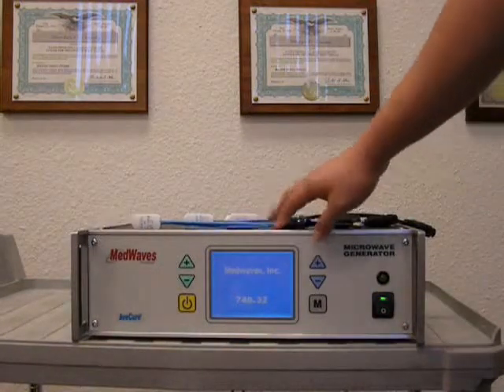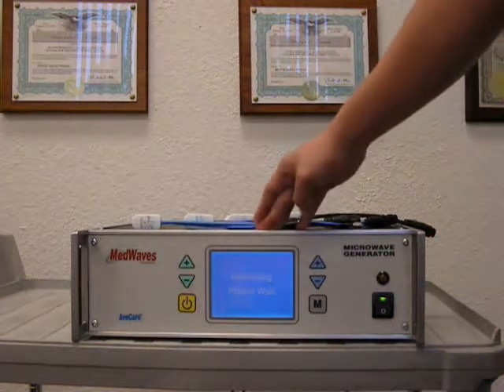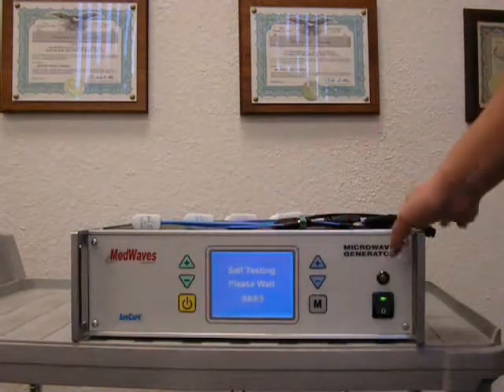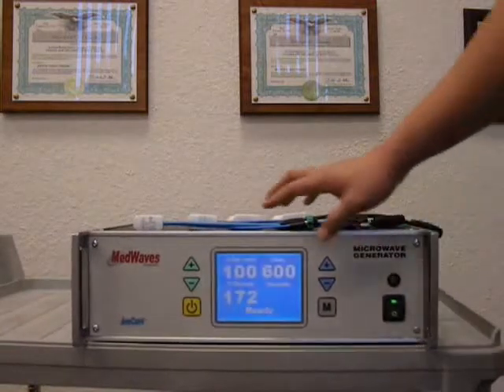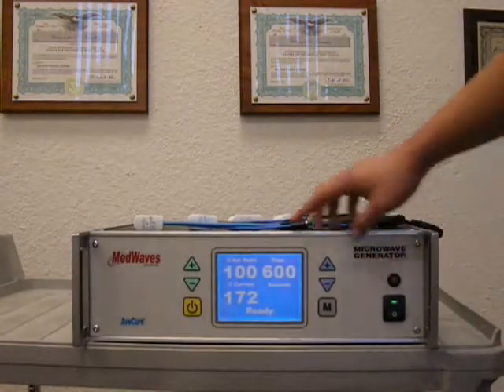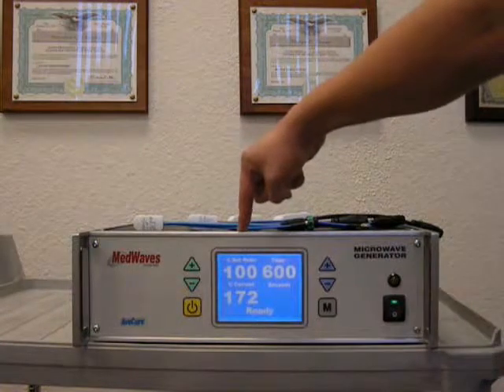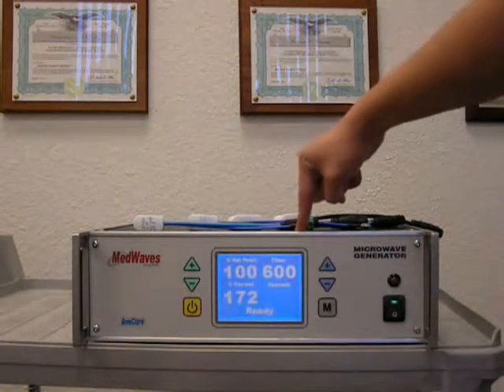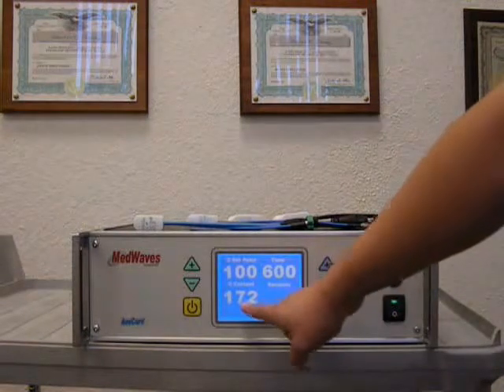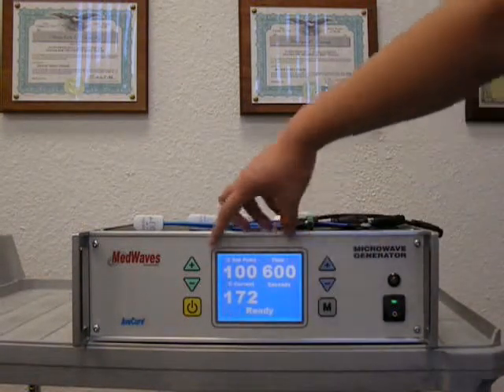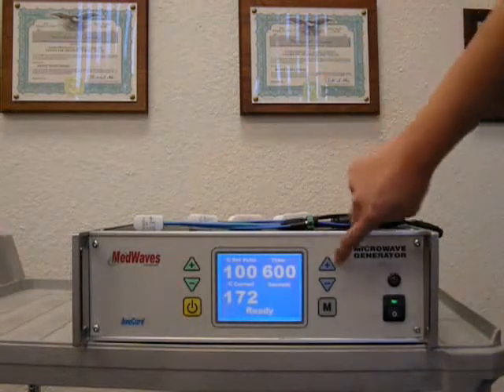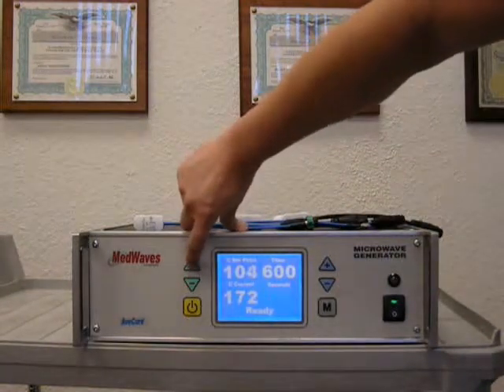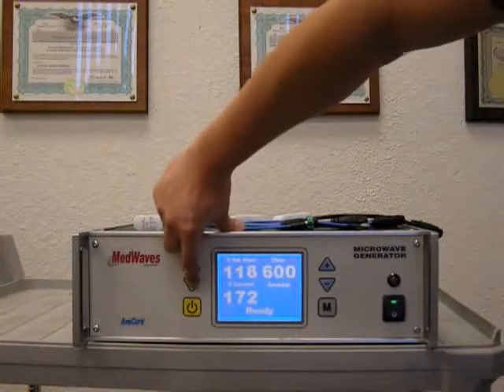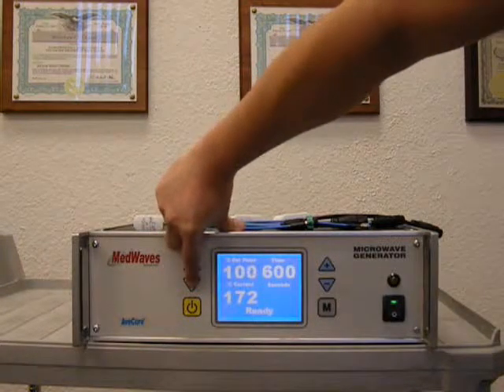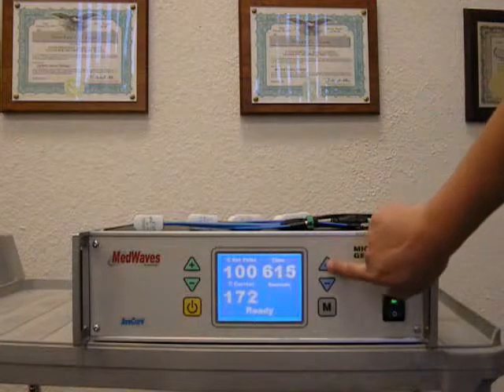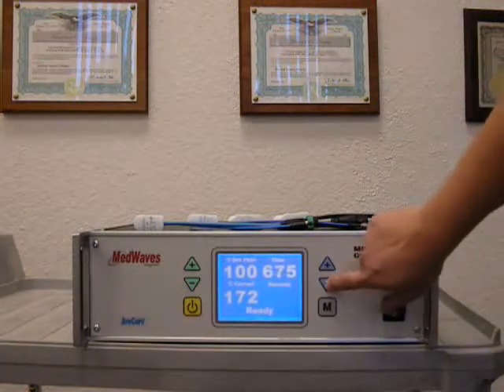So the generator will do its self-check procedure. And this is the ready screen. Here, as you can see, the generator will give you the temperature and the time setting. And then this is the temperature input from the probe. So you can adjust both of these using these arrows. When I hit up on here, the temperature increases. Down will decrease the temperature. Here, plus will increase the time, and minus will decrease the time.